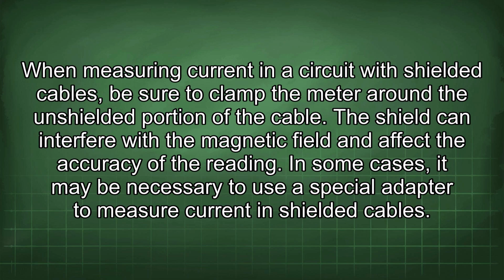When measuring current in a circuit with shielded cables, be sure to clamp the meter around the unshielded portion of the cable. The shield can interfere with the magnetic field and affect the accuracy of the reading. In some cases, it may be necessary to use a special adapter to measure current in shielded cables.